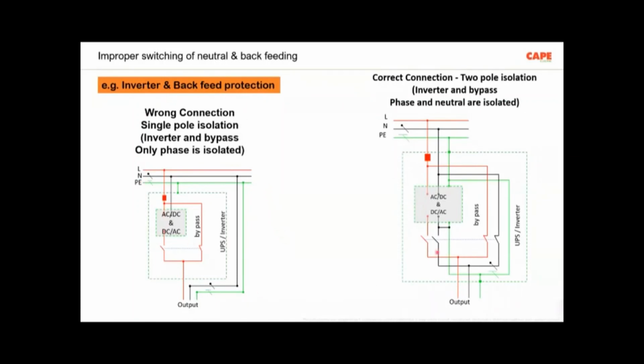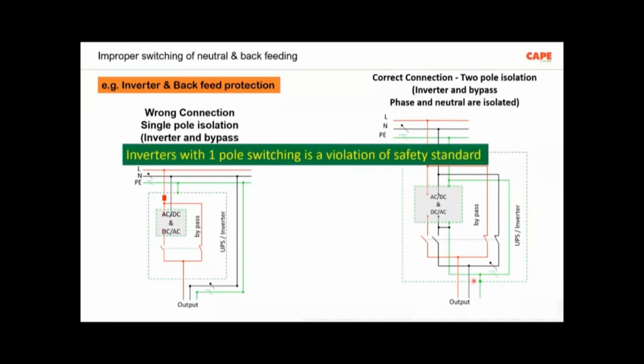So, while using inverters, please ensure that the requirement on the right side, which I am showing, is met: both the phase and the neutral must be isolated. Inverter or UPS circuits shall have separate neutral, and the neutral must be segregated from other parts of the wiring. But unfortunately, an inverter with two-pole isolation is quite rare in the market. We have to really search for it. So rather, I would make a statement that we actually use products which are inviting fire rather than protection.